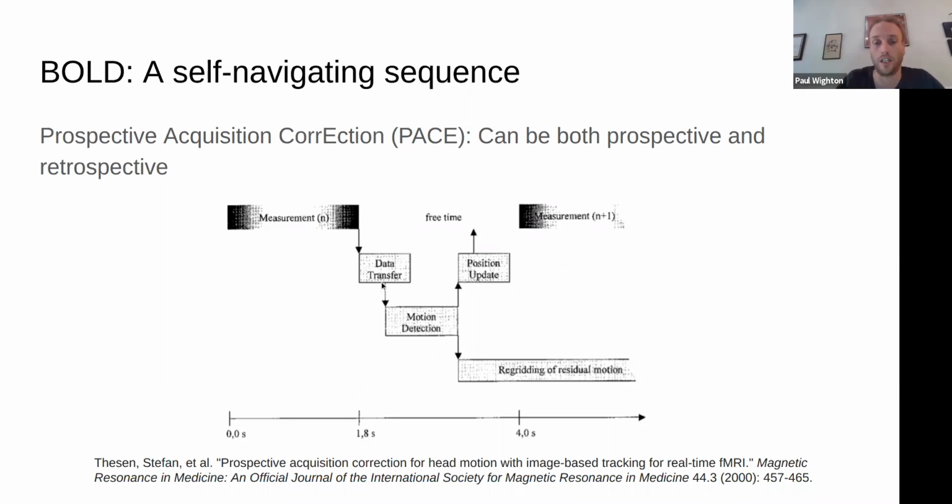it transfers it to a registration algorithm. That volume gets registered to the very first volume that was acquired. The motion estimates are computed. Everything we deal with here is rigid motion, so we're computing 6 parameters: 3 parameters for translation and 3 parameters for rotation. That's almost always the problem being solved in prospective motion correction. So that does a simple registration of 2 BOLD volumes, infers these parameters, sends it back to the scanner, the field of view is updated, and away you go.